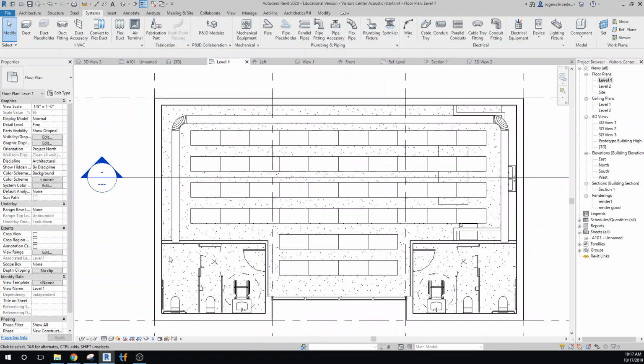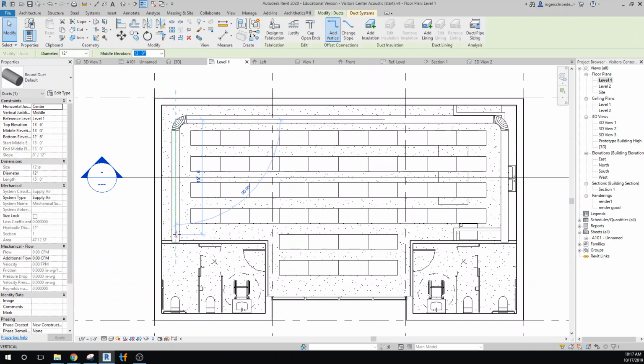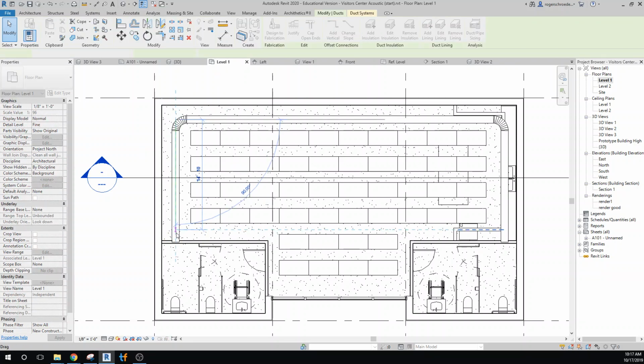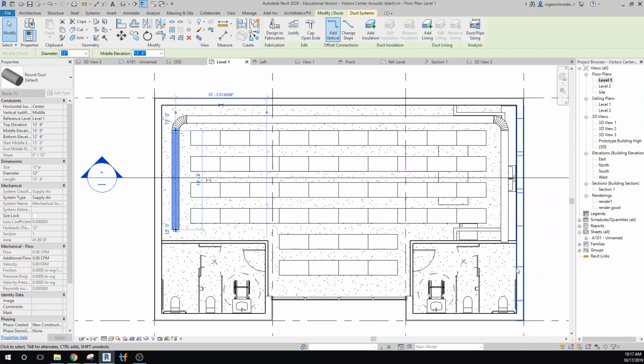The idea is this one could either be just a dead end termination - it doesn't even go to the wall. And the idea is that there's a supply over here that pushes the air around the room, and we can have all kinds of vents along here. They work, and they're quite effective because that's where we have a lot of convection of the cooling along the exterior wall surfaces. So this is a good way to supply heating and cooling air to the space.